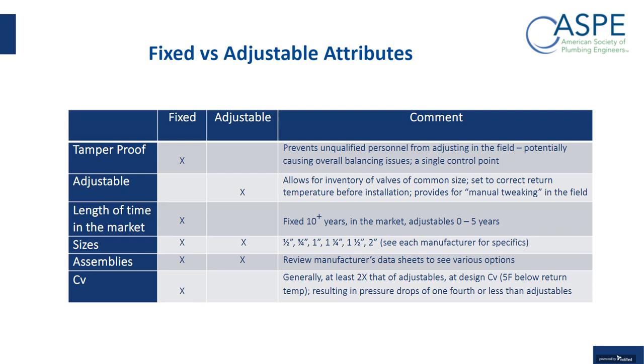So just some rough classification of the attributes of the fixed versus the adjustable. The fixed is tamper-proof, so it prevents unqualified personnel from adjusting in the field, potentially causing overall balancing issues, and it has a single control point. A lot of times you hear the expression, a facilities person has never met a knob he hasn't liked to turn. So that's just something to keep in mind.